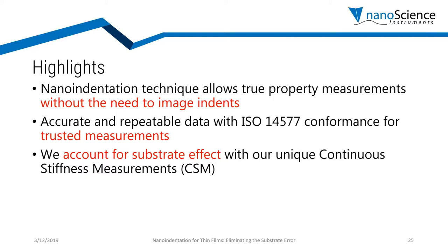To summarize the technique: nano indentation allows you to measure thin film properties without needing to image the indent, eliminating user errors. Because of our electromagnetic actuator, we perform very repeatable measurements since it is a linear system with no coupling errors. And we account for the substrate effect in thin film property measurement using Continuous Stiffness Measurement. There is a mathematical model applied to account for the substrate effect, which I will discuss further.